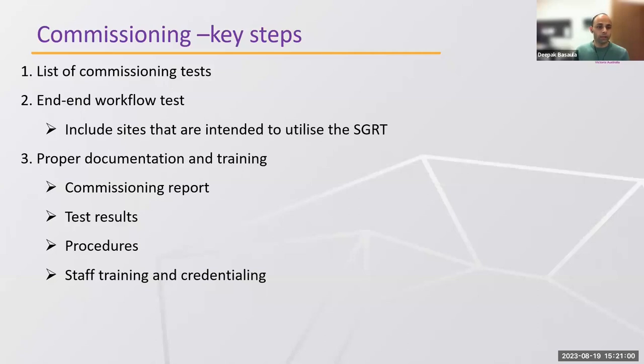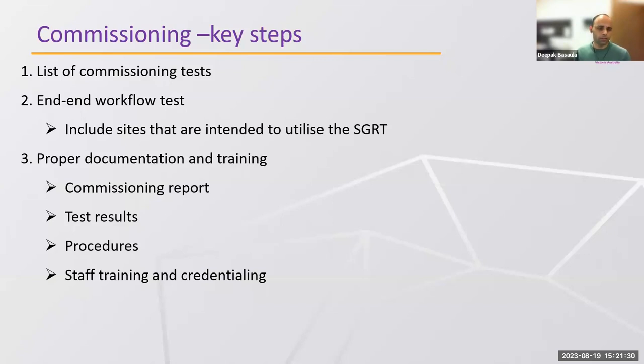TG-302 refers back to TG-140 for the test list. You need to confirm your machine isocenter is correct before moving to SGRT, and test your coordinate system — does it match your TPS, linac system, etc.? The SGRT shift data is from your isocenter coordinate, and you need to understand and interpret that correctly in the clinic. You'll need to compile a list of equipment required to perform the commissioning tests. Useful items include a mannequin, which allows testing of many scenarios, a 4D thorax phantom that can move up and down for dynamic accuracy testing, and a calibration cube with radio-opaque objects in the center for CT-based calibration.